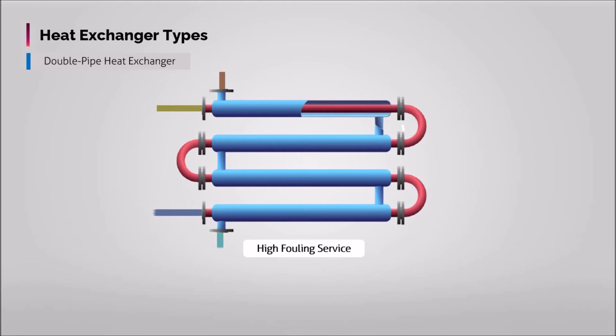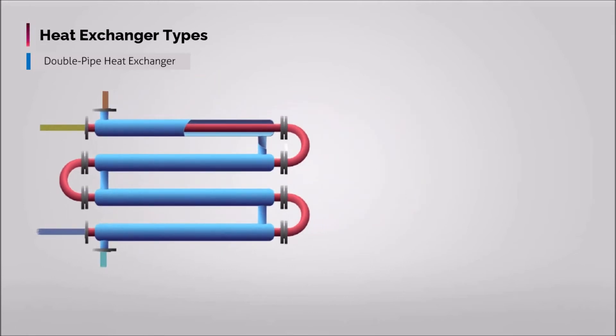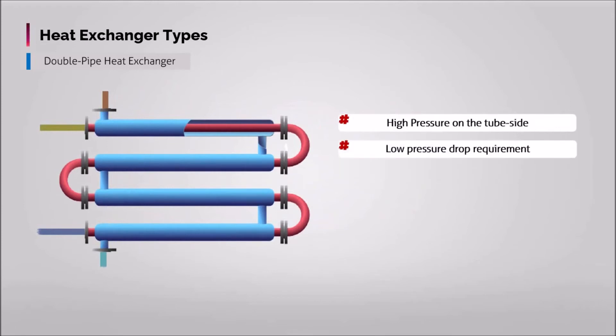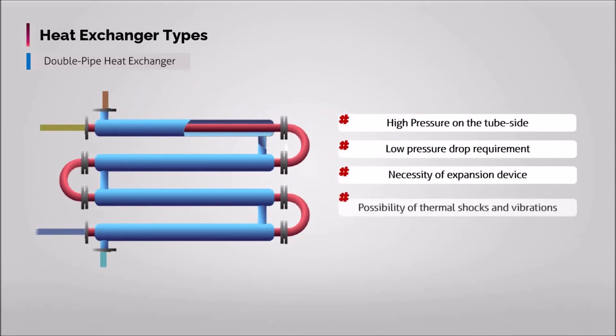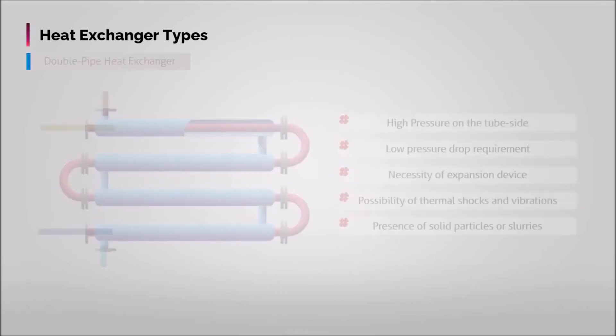Multi-tube exchangers are utilized when higher heat duties are required. A double pipe exchanger should be used when one or more of the following criteria apply: high pressure on the tube side, requirement of lower pressure drop on one side, necessity of an expansion device to improve the heat transfer coefficient, possibility of thermal shocks and flow-induced vibrations, or presence of solid particulates or slurries.